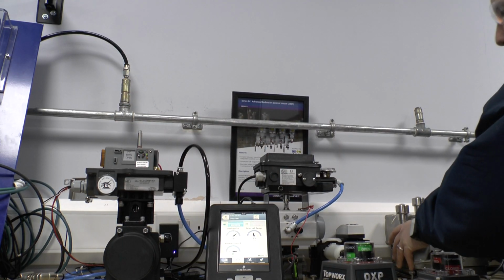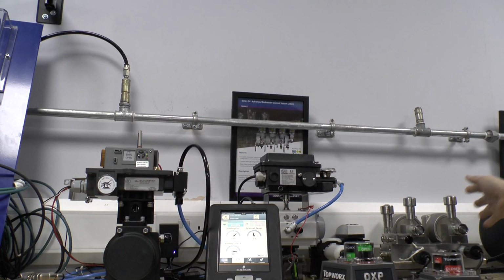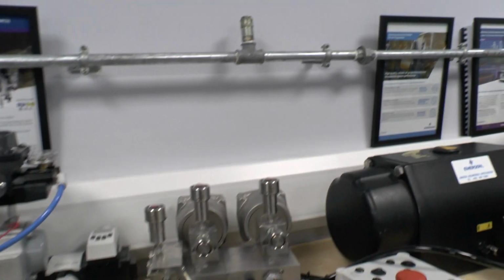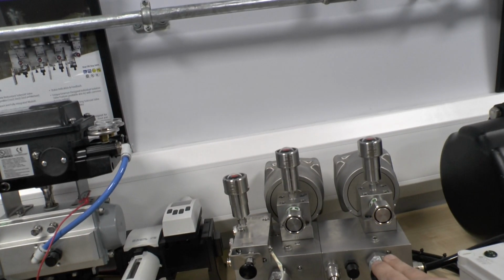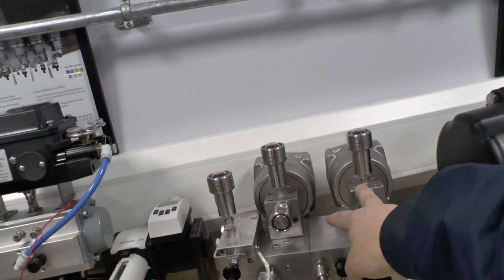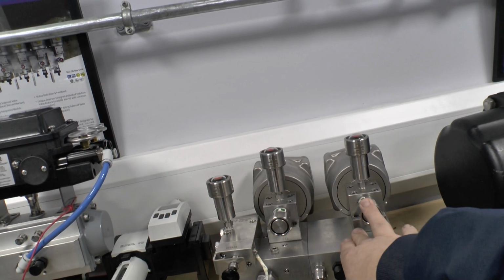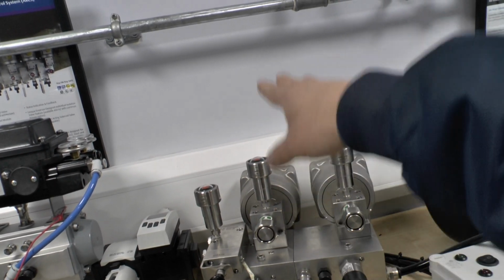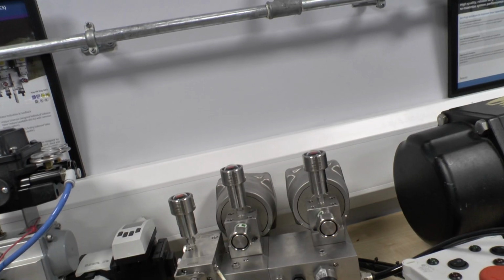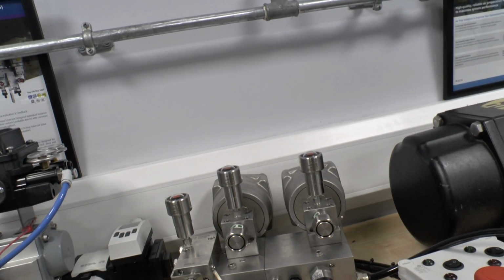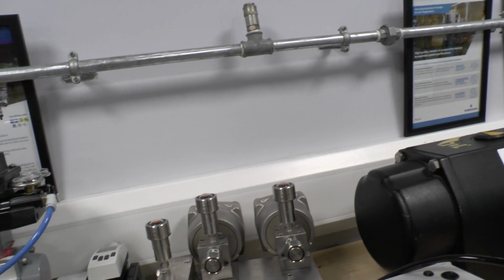Just over on the other side here we have an example of an ASCO RCS. This is a 2 out of 2 system. We've got two valves, and the way it operates is you power both devices, and if one of the devices fails, it goes to the next device and ensures the system is completely open all the time.